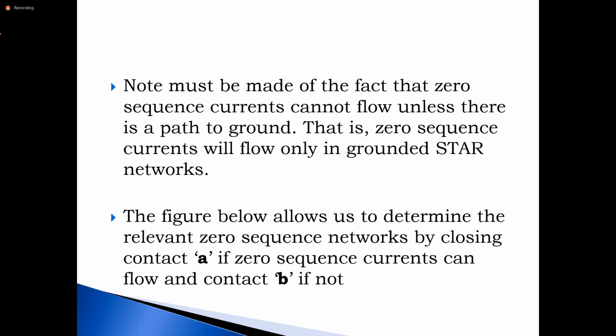All right? And to make the determination in terms of the zero sequence for your transformer, we use a network and we say here, if zero sequence can flow, yes, you close contact A, and if zero sequence cannot flow, you close contact B.